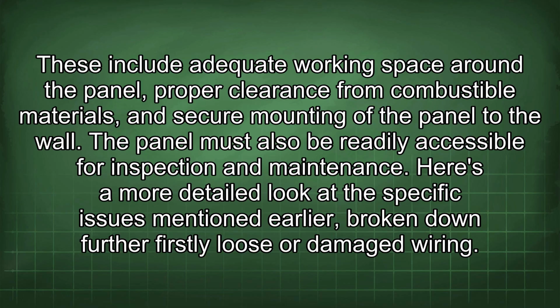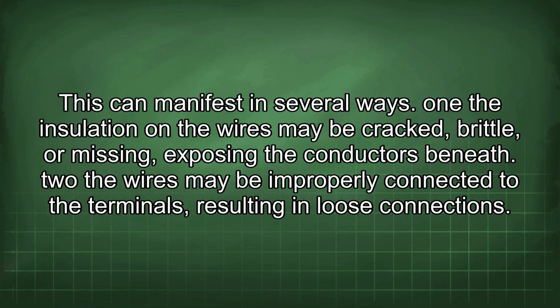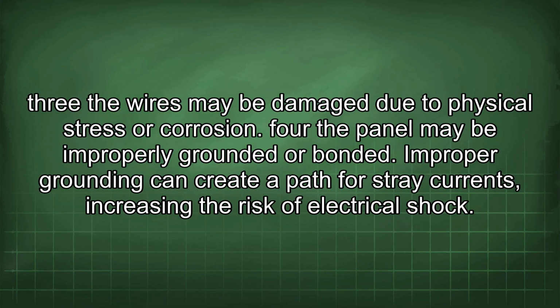Firstly, loose or damaged wiring. This can manifest in several ways. 1. The insulation on the wires may be cracked, brittle, or missing, exposing the conductors beneath. 2. The wires may be improperly connected to the terminals, resulting in loose connections. 3. The wires may be damaged due to physical stress or corrosion. 4. The panel may be improperly grounded or bonded.